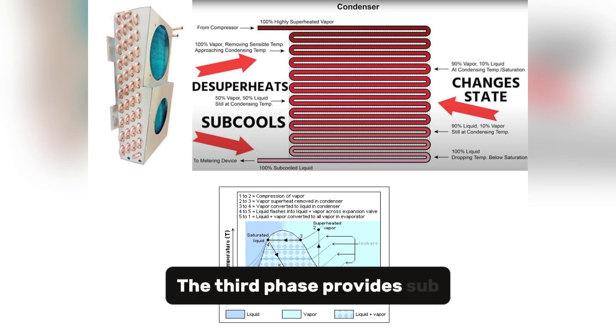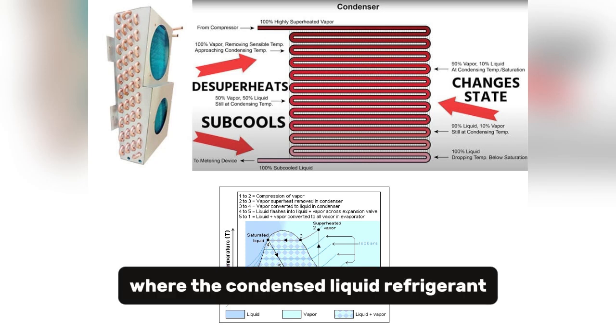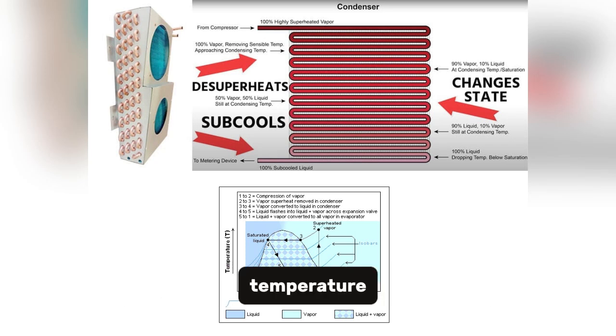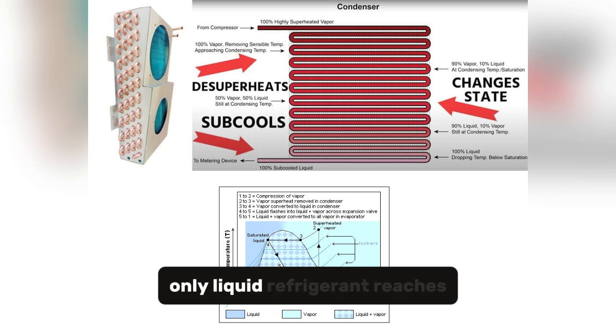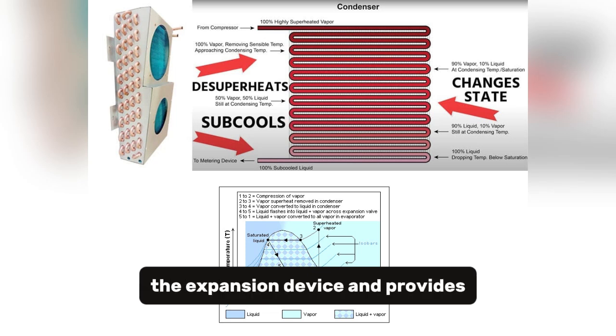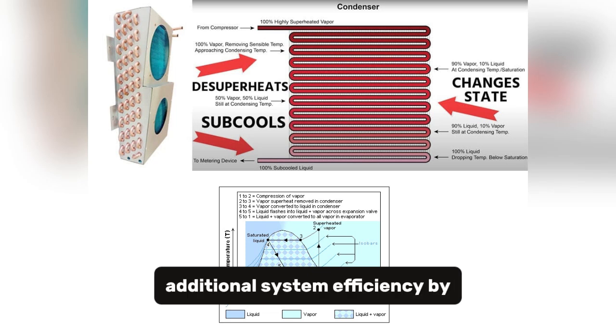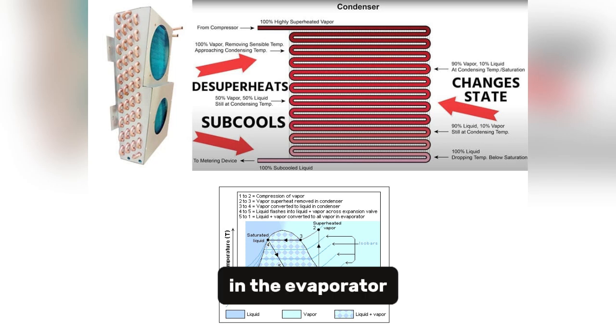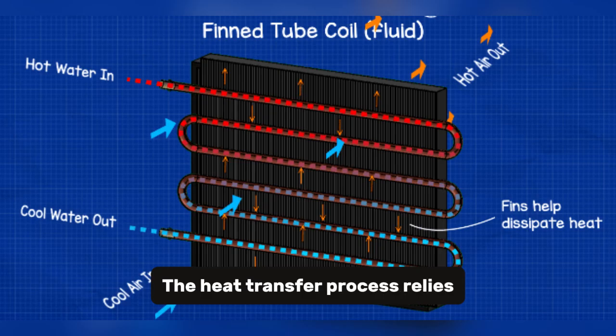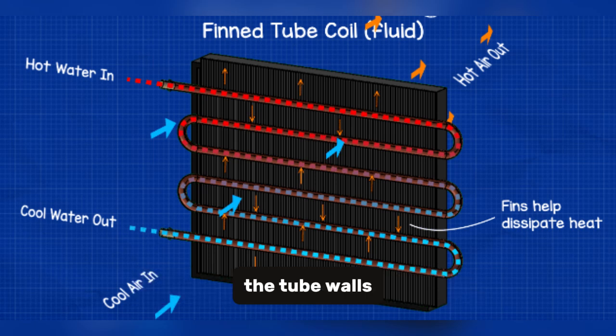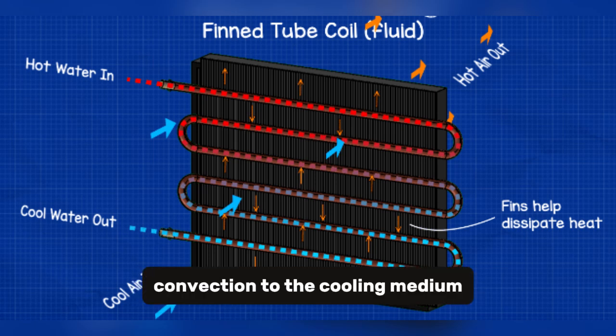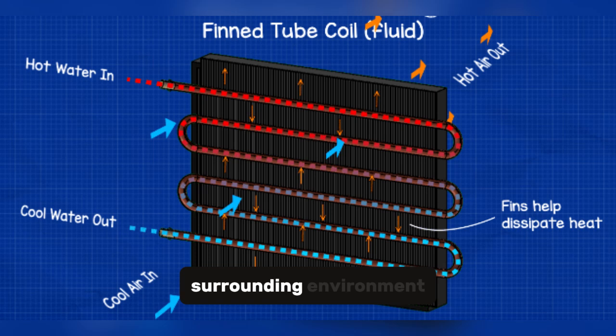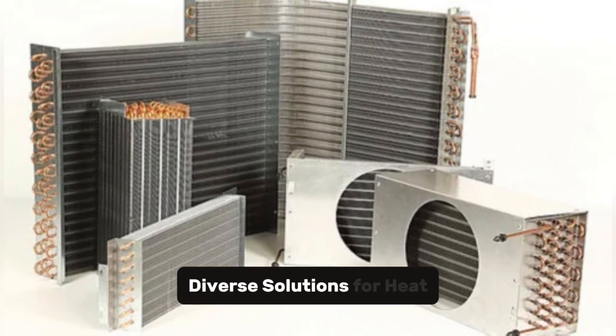The third phase provides subcooling, where the condensed liquid refrigerant is cooled below its saturation temperature. This subcooling ensures that only liquid refrigerant reaches the expansion device and provides additional system efficiency by increasing the refrigerant's cooling capacity in the evaporator. The heat transfer process relies on 3 modes: conduction through the tube walls, convection to the cooling medium, and often radiation to the surrounding environment. The condenser must facilitate all 3 modes efficiently while managing refrigerant flow and pressure drop. Types of condensers. Diverse solutions for heat rejection.